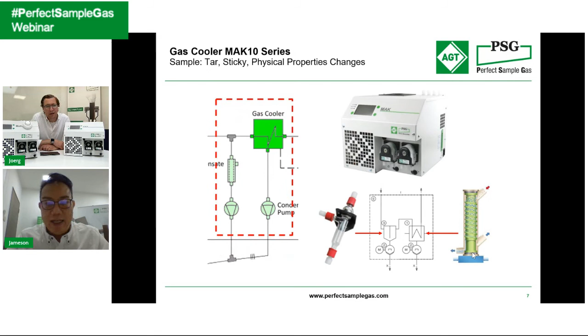If you're doing an FGD application, flue gas desulfurization, you have to find out whether it's a dry application or a wet application. If it's a wet application, normally they use water with caustic or sodium hydroxide to remove the acidic flue gas by neutralizing it, injecting alkaline. Once that flue gas becomes alkaline, it can easily wash out.